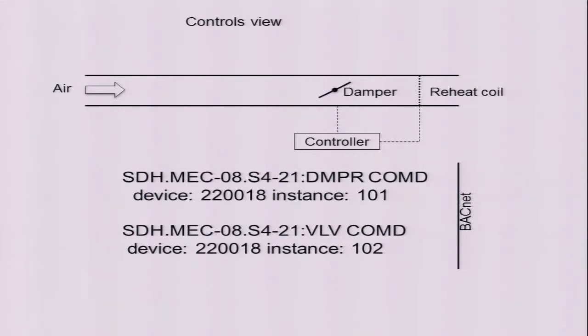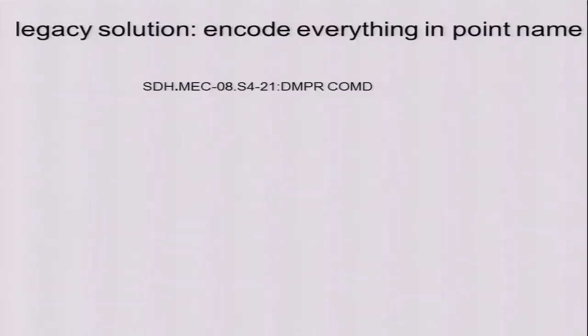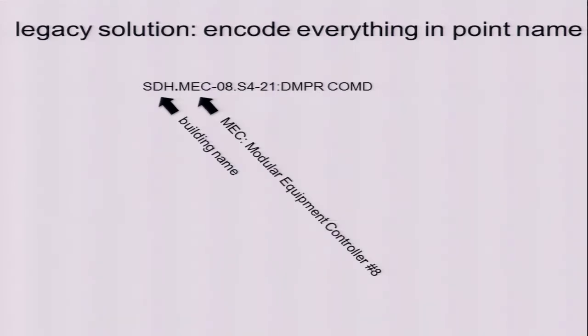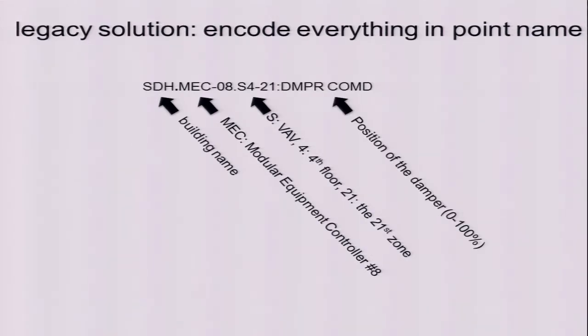These names are confusing, they actually encode a whole bunch of information. It tells you the building, the modular equipment controller number, which relates to the network and how the controllers are interconnected, the floor, the zone, and finally the component, like the damper. So that's an example of what the status quo looks like for controlling buildings.